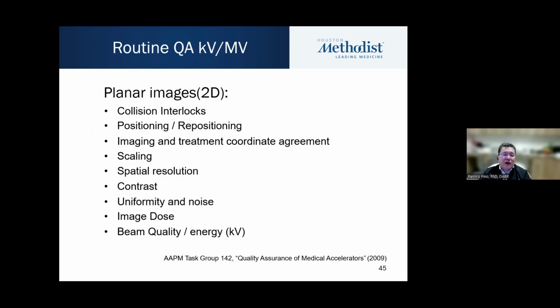In terms of routine QA for kilovoltage and megavoltage imaging, collision interlocks are important. Typically, these are C-arm systems, except for tomotherapy and the Halcyon, which are ring-based. So collision interlocks are important. Position and reposition is one of the most important tests that you can perform on a daily basis, as well as imaging and treatment coordinate agreements.